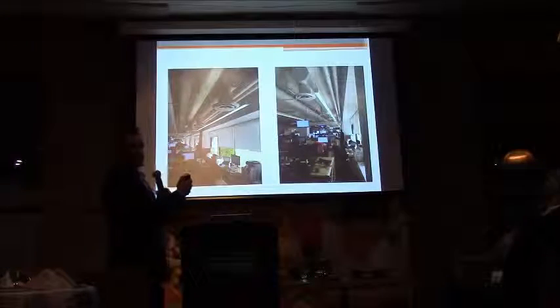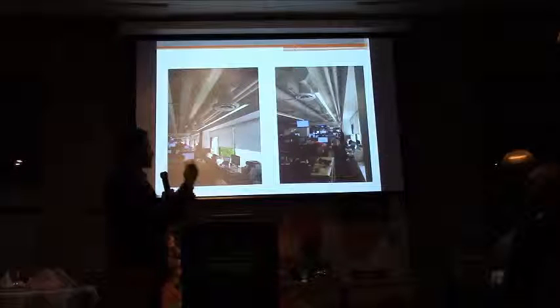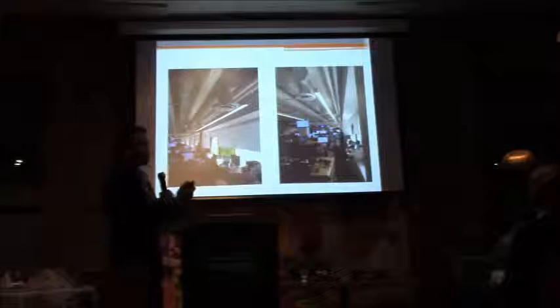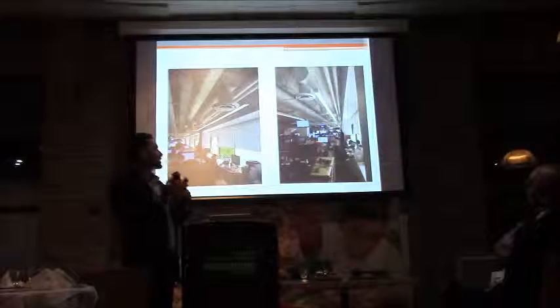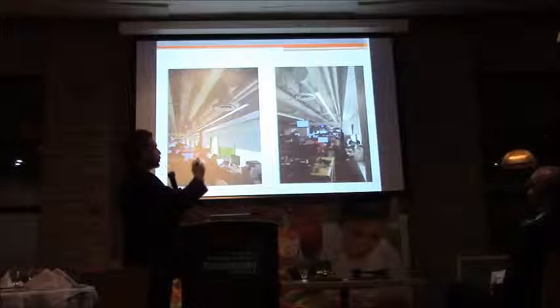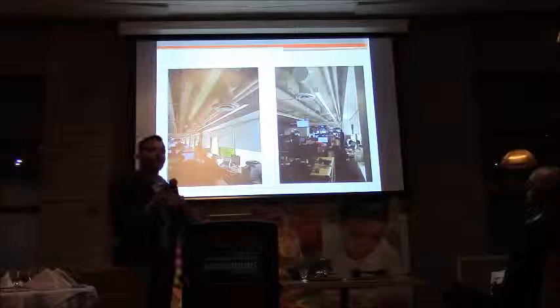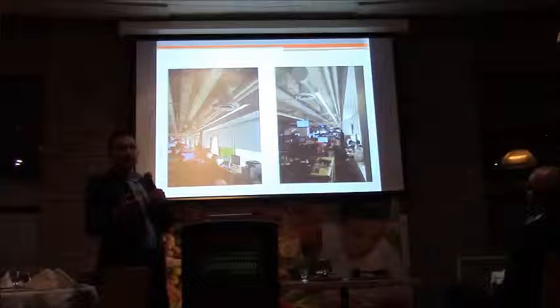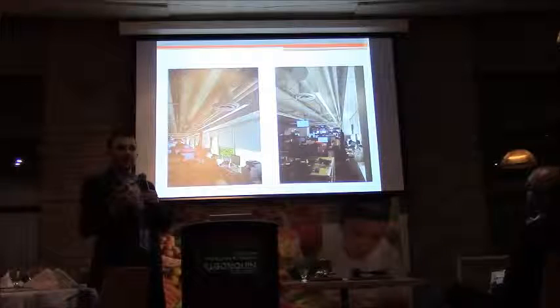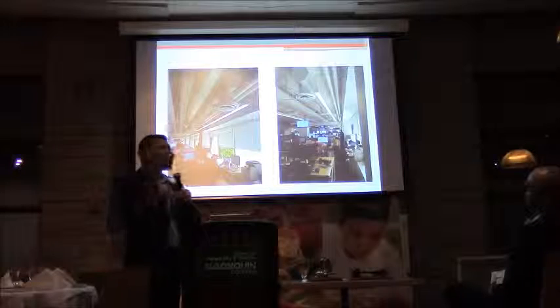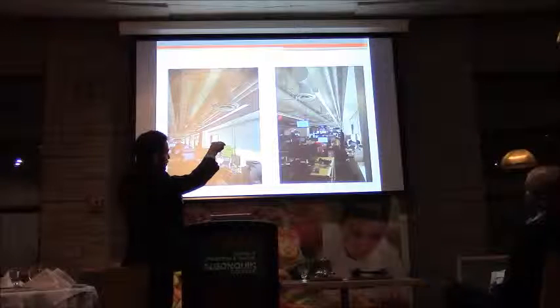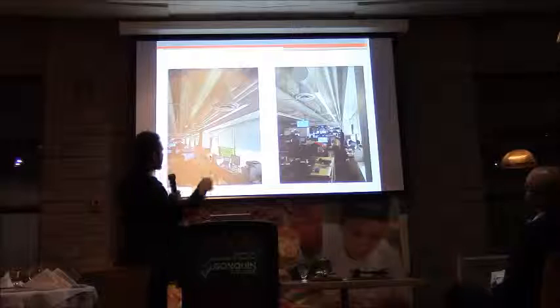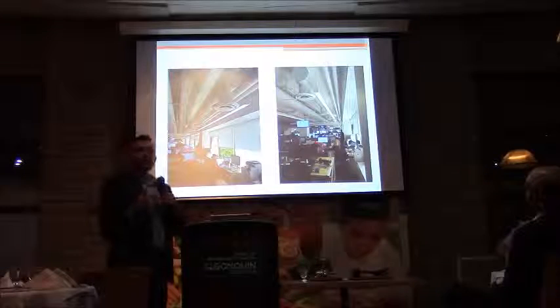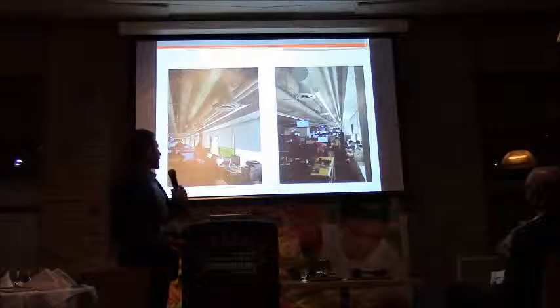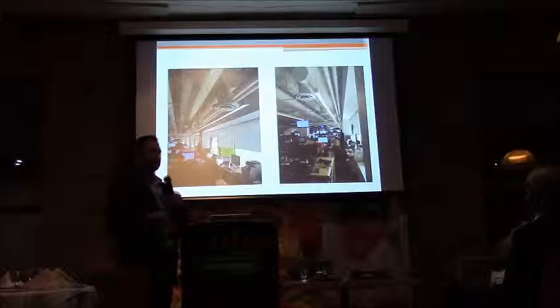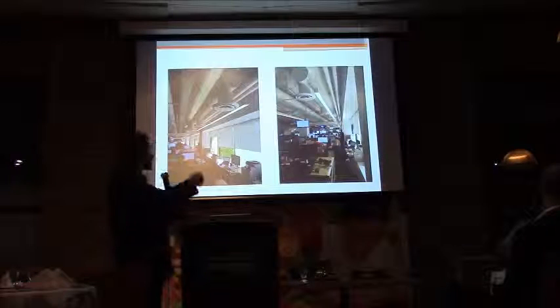The reason these diffusers have been taped off is because, like I said, we have a variable air volume system. Whenever the air modulates down, for the people who work on the weekend shift, there are fewer people than on the weekday shift, so the heat load is lower and the airflow modulates lower. So everybody sitting under one of these diffusers is getting cold air showers on their body. We got a call where they asked us to come take a look at their ventilation system and propose a product for them. And that's exactly what we did.